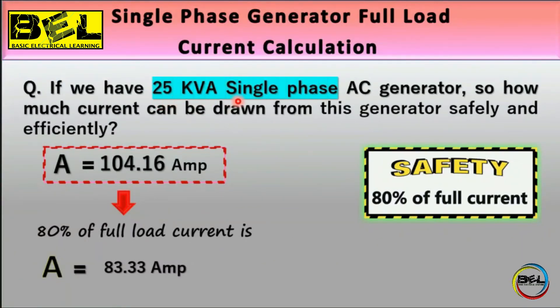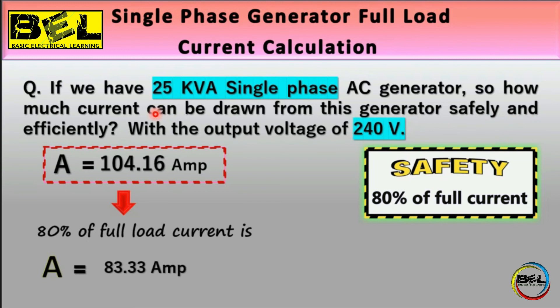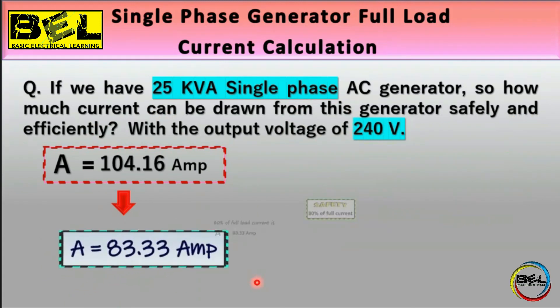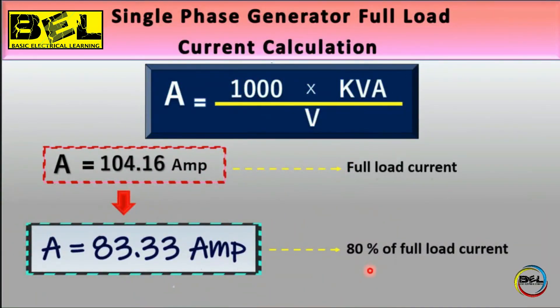In summary: for a 25 kVA single phase AC generator with 240 V output, the full load current is 104 amperes, and the safe operating current is 83.33 amperes — which is 80% of the full load current. We always apply 80% because of the power factor. The formula is: A = (1000 × kVA) / V, and this applies to single phase only. For three phase AC generator calculations, a separate link is provided.